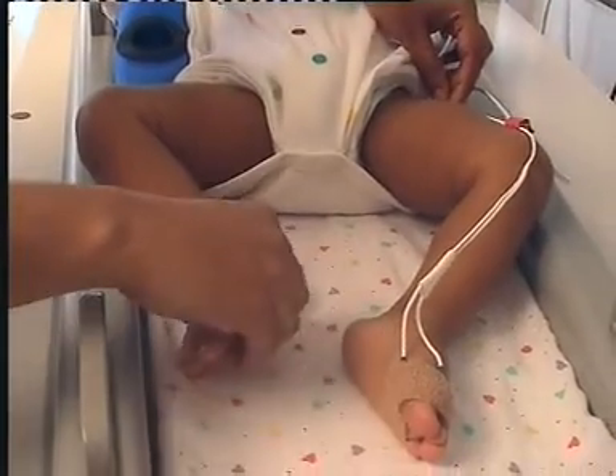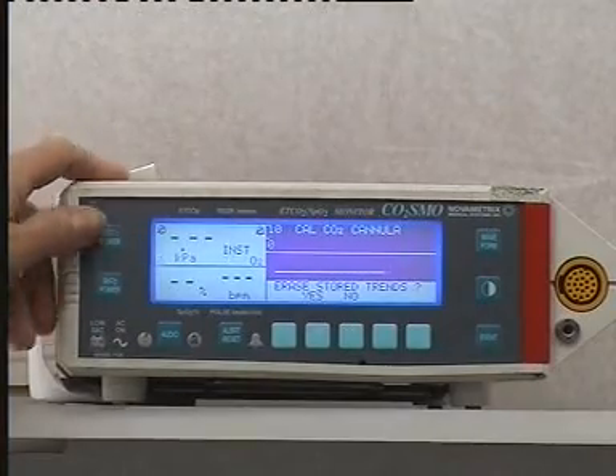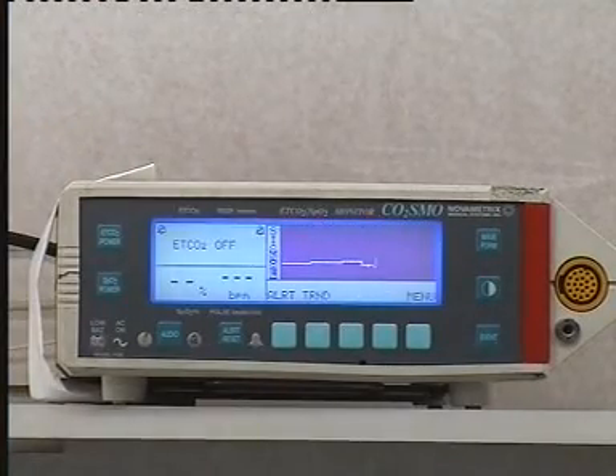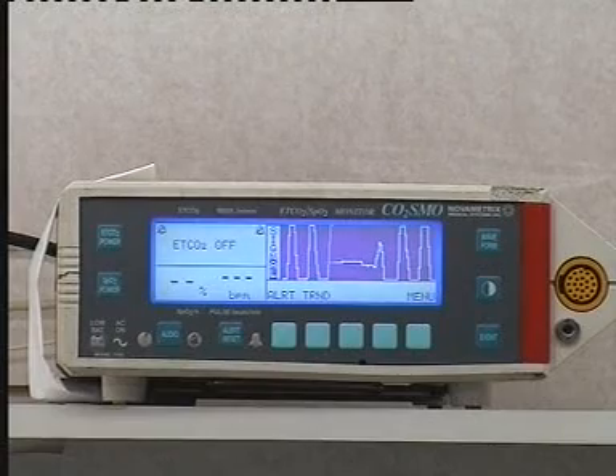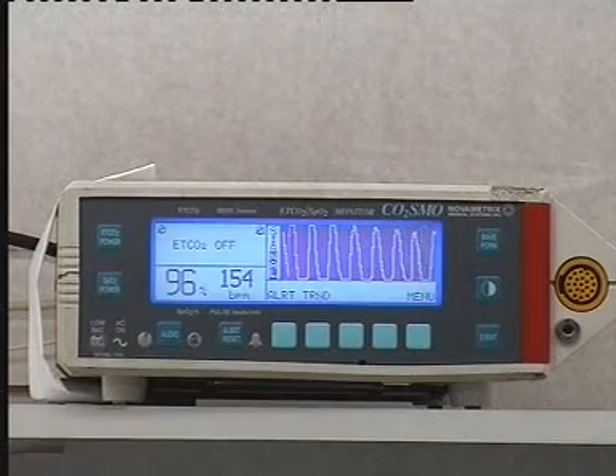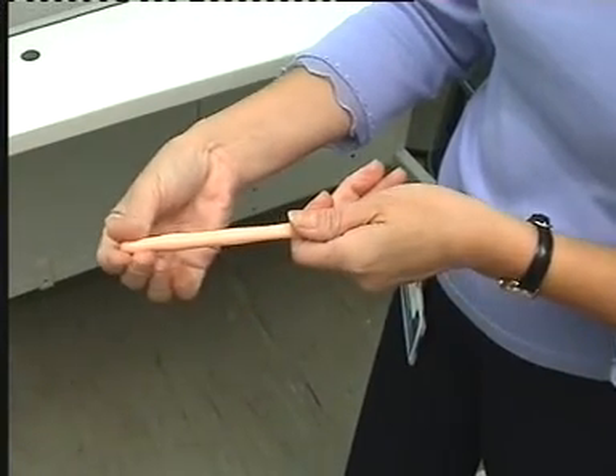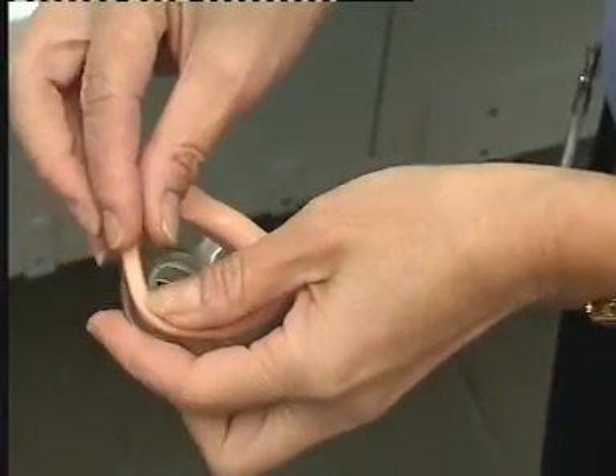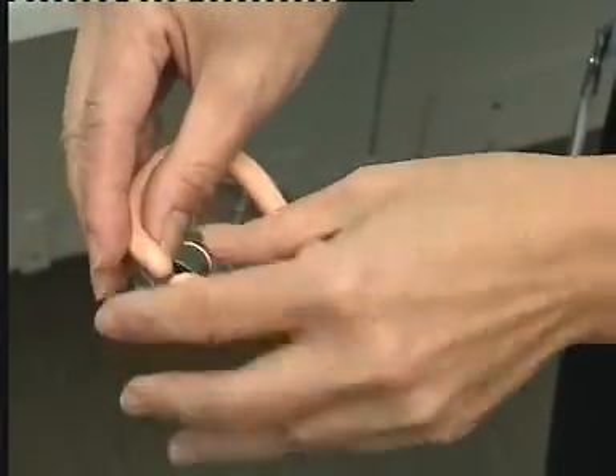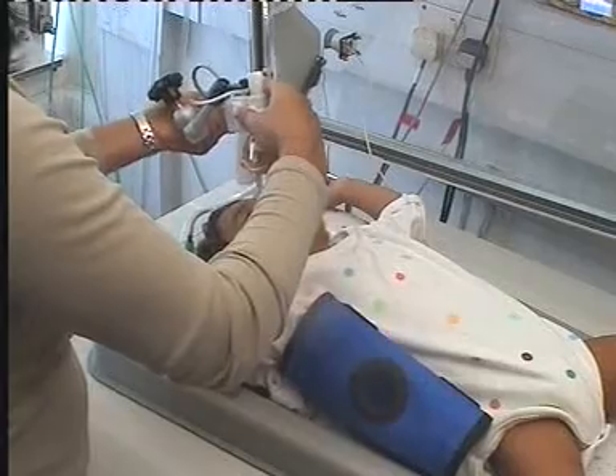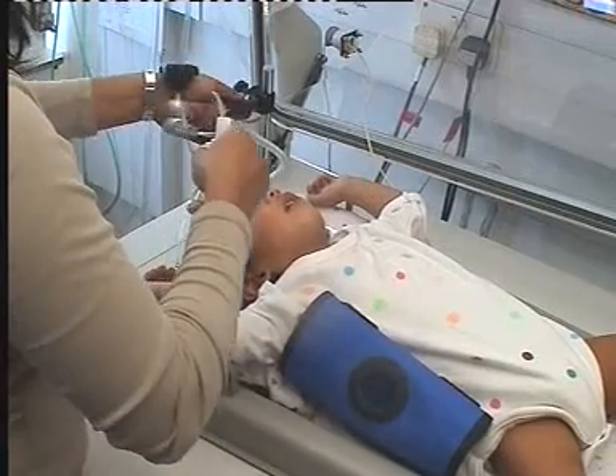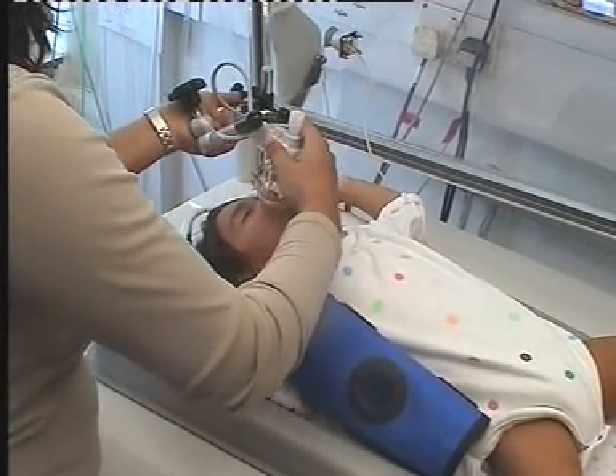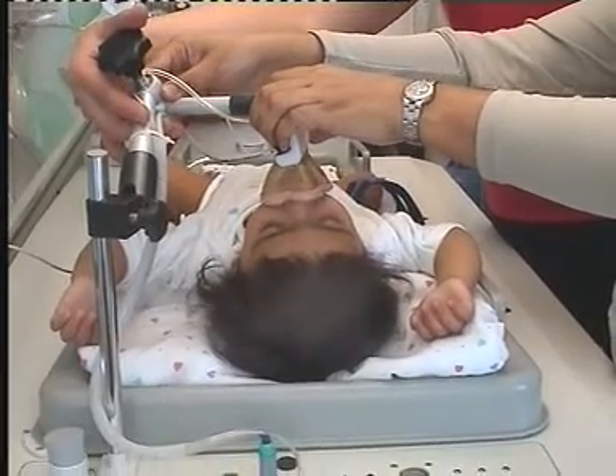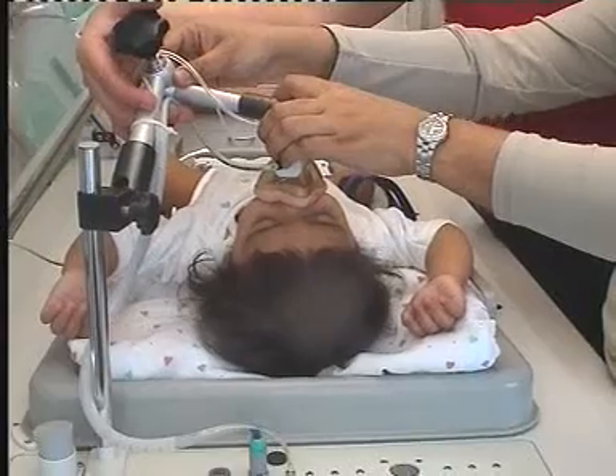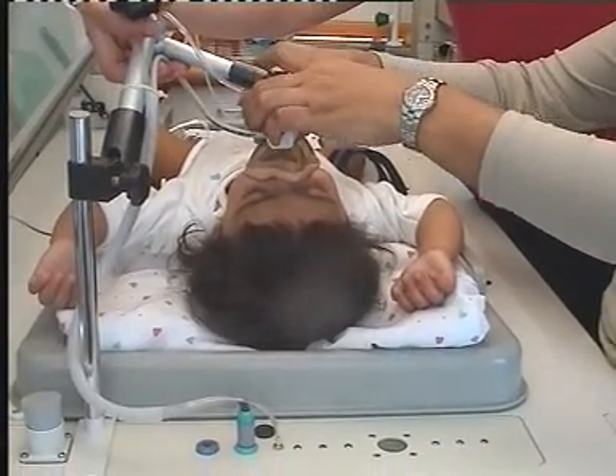A pulse oximeter sensor is attached to the baby's foot to monitor heart rate and oxygen levels throughout the entire testing procedure. During the breathing tests, the baby will breathe through a small face mask. This is gently sealed to the face using a ring of soft putty. The mask, which is attached to the pneumotach and shutter, is placed over the mouth and nose to record changes in flow and pressure at the airway opening.